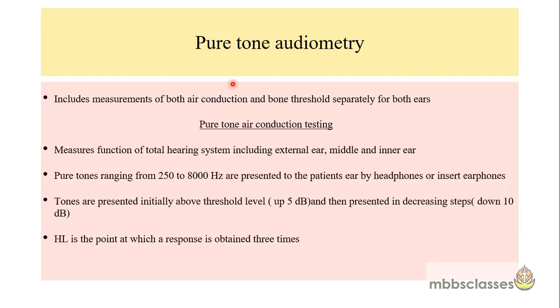Pure tone audiometry includes measurement of both air conduction and bone conduction hearing thresholds separately for right and left ears. Air conduction threshold testing measures the function of the total hearing system including the external ear, middle ear, and inner ear. Pure tones ranging from 250 to 8000 Hz are presented via headphones or insert earphones. The tones are initially presented above the threshold by 5 dB, then decreased in 10 dB steps, and the hearing threshold is the point at which a response is obtained three times.